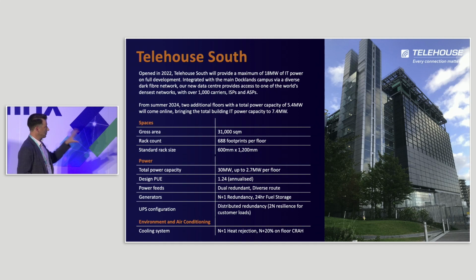So a bit about it: 15 megawatts was the original building itself when Reuters had it. After our design, we're now sitting at a 30 megawatt building, so we've doubled the amount of power going into the building, and that's equaling a 7 megawatt IT load from the Reuters day to an 18 megawatt IT load on full fit-out of our deployment. We're redoing all of the office floors, which you'll see in a few later slides - all of the office floors in the building are now turning into white space, with the option of offices/white space on level 8 as well.